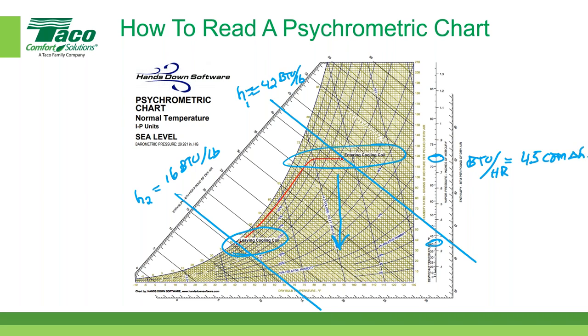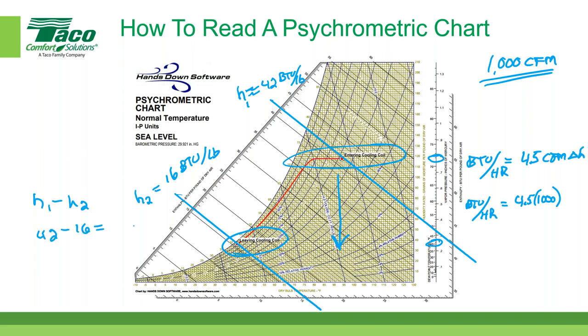There's the delta H. So let's assume our system was using a very simple 1,000 CFM, Brett? Yep. 1,000 CFM. We like doing things with round numbers. So the BTUs per hour is equal to 4.5 times 1,000 times the difference in enthalpy, H1 minus H2, which we just said. 42 minus 16 equals 26. So we'll put that in there, 26.